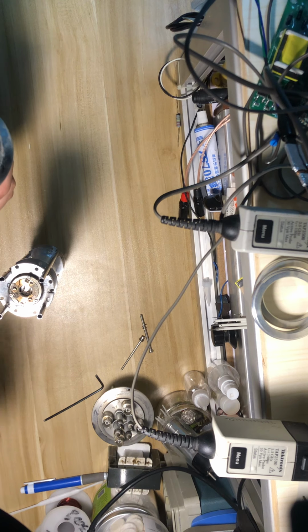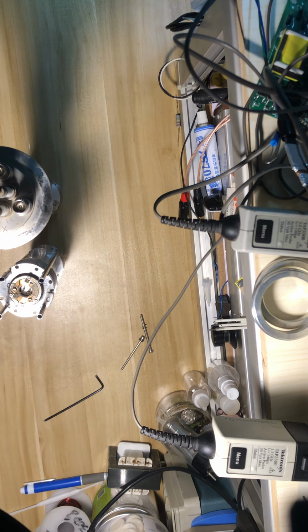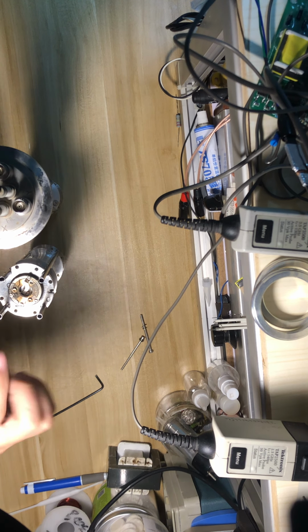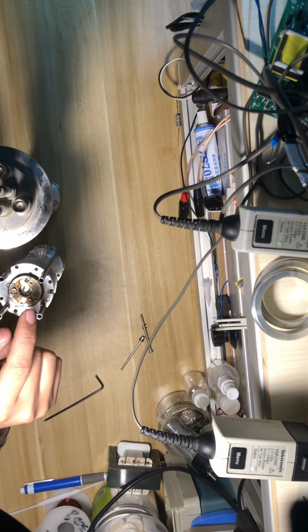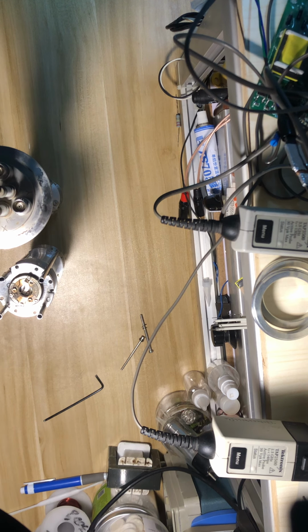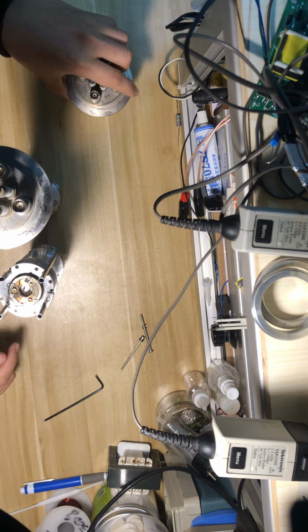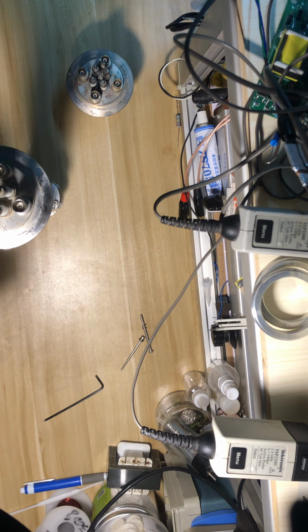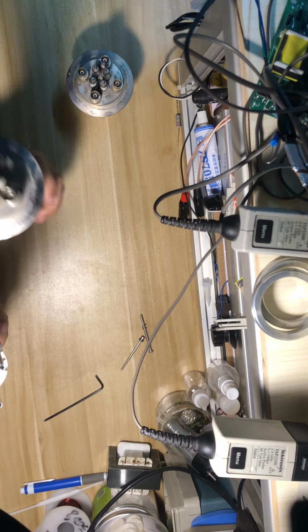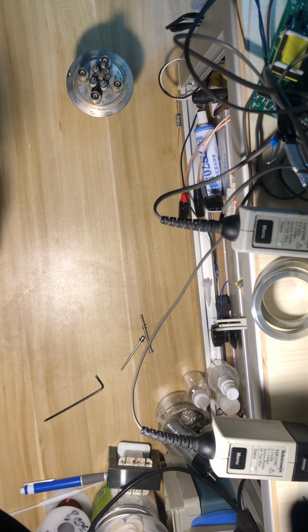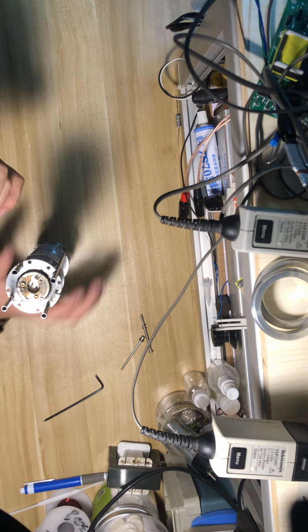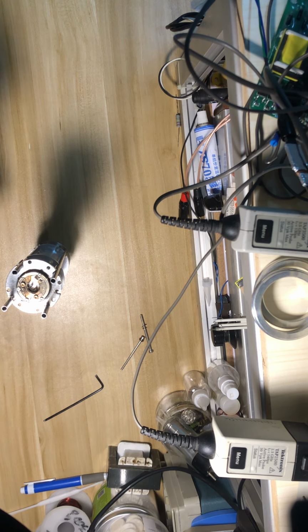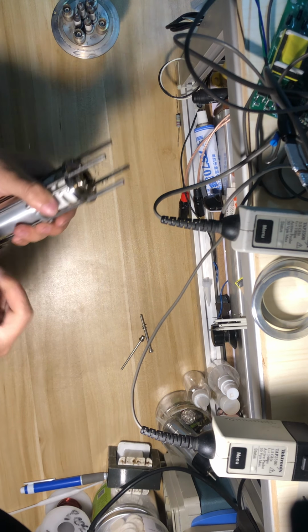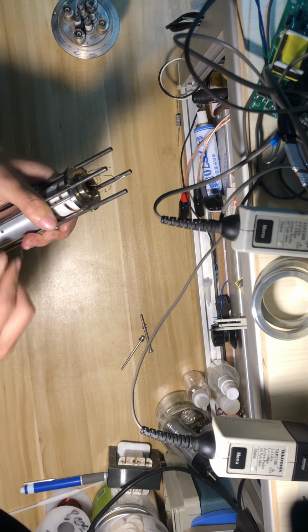Here I have a gun assembly being taken apart. So under this, there's basically a high vacuum seal and the electrical connection and the high voltage insulation. It's being screwed on this stainless steel wire to make an electrical connection between the connector and the real part. So now we are looking at the filament assembly. This is actually not only the filament assembly. This contains the Wehnelt hole or the grid. So you will see it in here, the grid. Okay. So now we will take the screw out and we will see it.